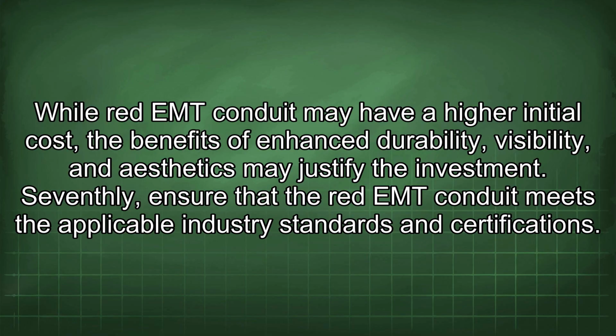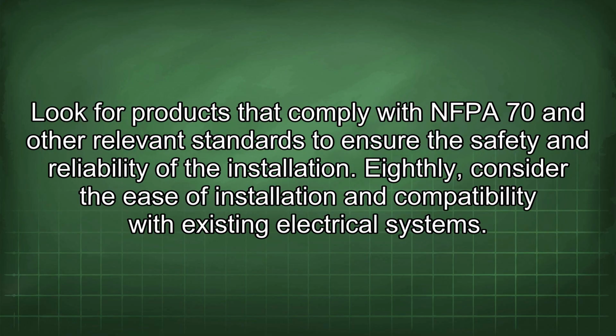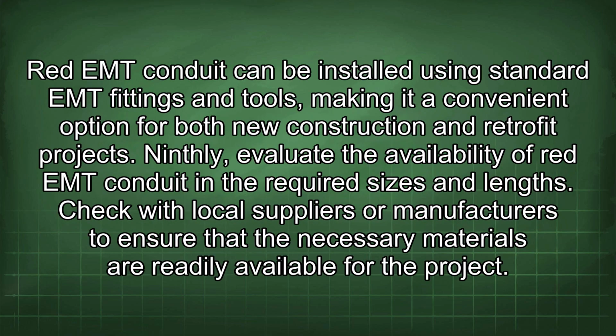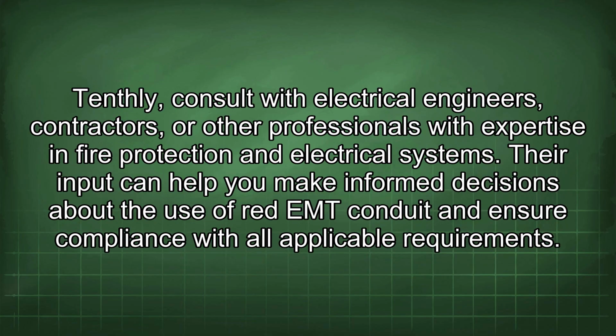Seventhly, ensure that the red EMT conduit meets the applicable industry standards and certifications. Look for products that comply with NFPA 70 and other relevant standards to ensure the safety and reliability of the installation. Eighthly, consider the ease of installation and compatibility with existing electrical systems. Red EMT conduit can be installed using standard EMT fittings and tools, making it a convenient option for both new construction and retrofit projects. Ninthly, evaluate the availability of red EMT conduit in the required sizes and lengths. Check with local suppliers or manufacturers to ensure that the necessary materials are readily available for the project. Tenthly, consult with electrical engineers, contractors, or other professionals with expertise in fire protection and electrical systems. Their input can help you make informed decisions about the use of red EMT conduit and ensure compliance with all applicable requirements.